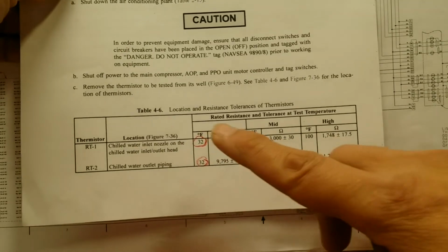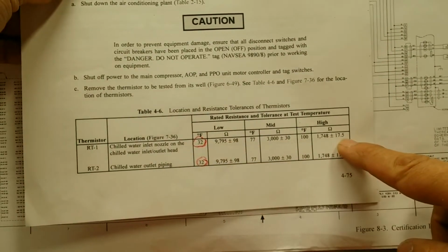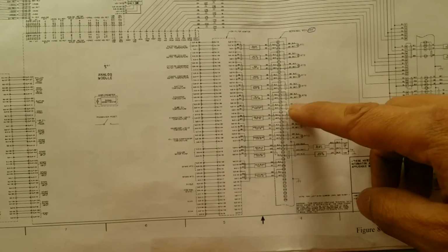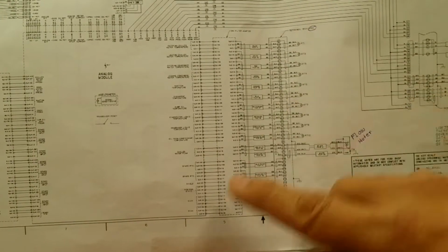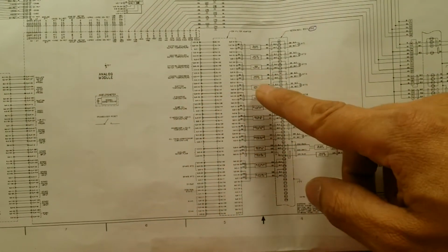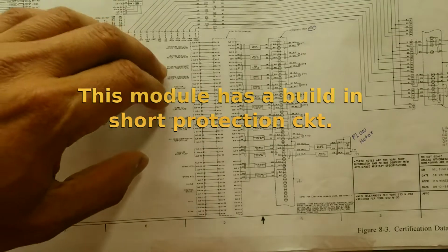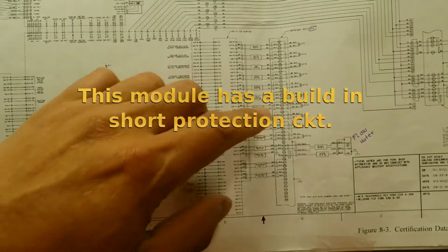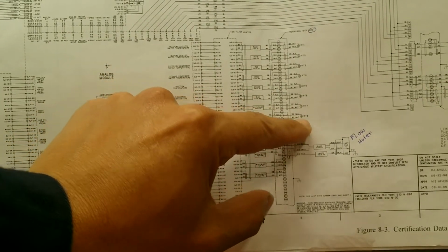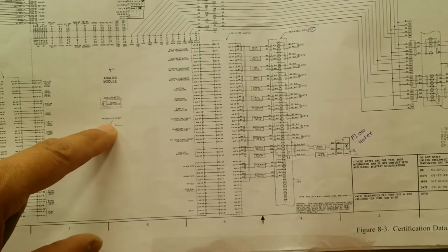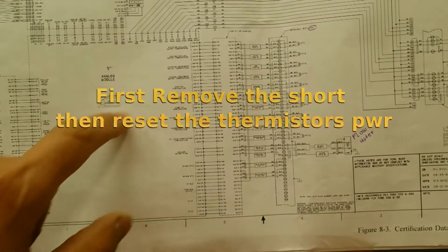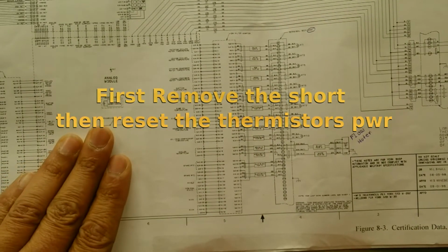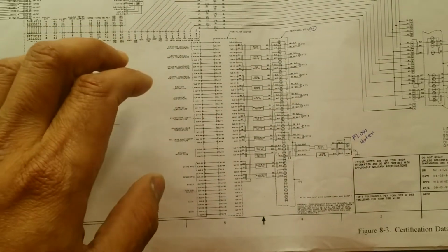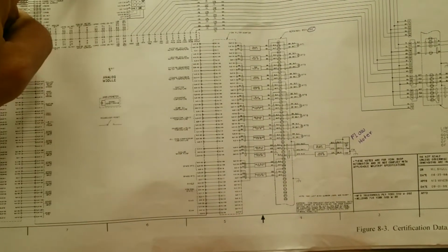Now, a moment ago I told you that the thermistors have to have a certain resistance, but what happens if a thermistor shorts, or a cable to a thermistor shorts? That will create a short condition. The analog module is always putting 28 volts to all of them, so it will disconnect power to not just that one thermistor, but all of them. You will have to troubleshoot and fix the short, and then press the transducer reset button so that all the transducers start working again. This button is located on the circuit card of the analog module. The analog module is located under the microprocessor module.